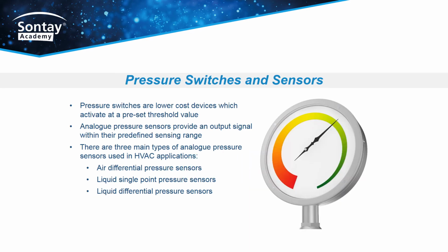Pressure switches and sensors. Pressure switches are lower cost devices which activate at a preset threshold value. Analog pressure sensors provide an output signal within their predefined sensing range. There are three main types of analog pressure sensors used in HVAC applications: air differential pressure sensors, liquid single point pressure sensors, and liquid differential pressure sensors. This presentation focuses on analog sensors.